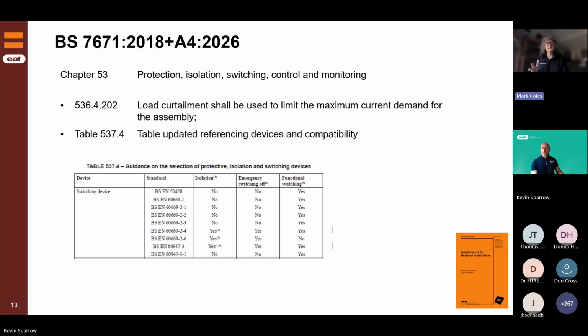We've been in discussions with ENA. So you think about it, you've got a heat pump going in, you've got EV charging, you've got other loads going on. And if you follow, for instance, what's in IET guidance, still in guidance note 1 and also the On-Site Guide, you can come out with super duper values of 160 amps, 200 amps for a dwelling. And when people were following guidance on this and then putting a request into the DNO and saying, we've got 100 amps on this supply, can I upgrade it to 180? And they're going, what on earth do you need that for?